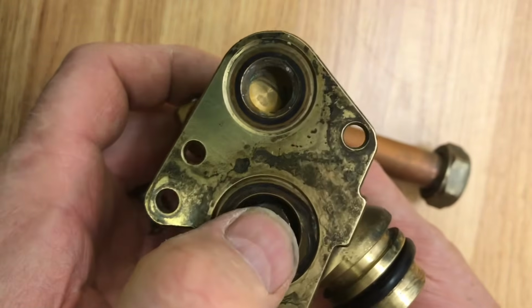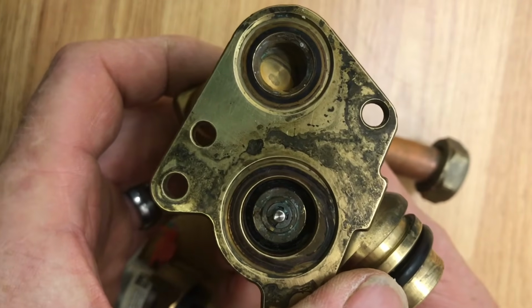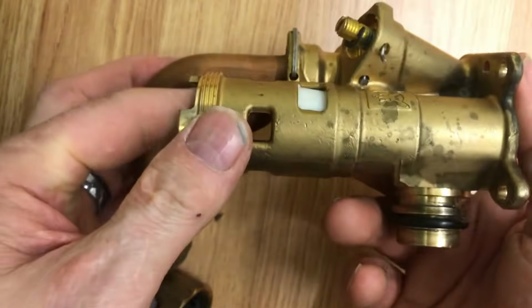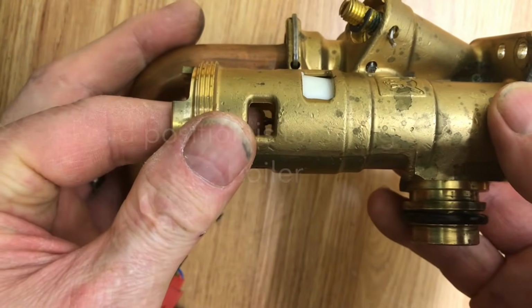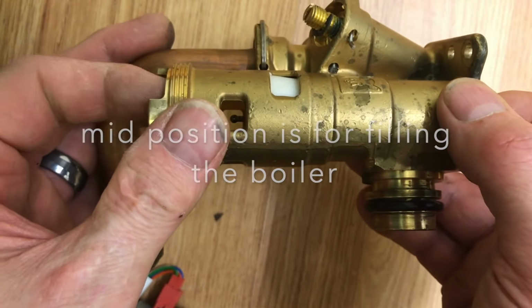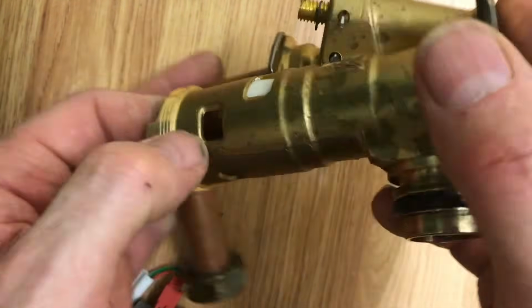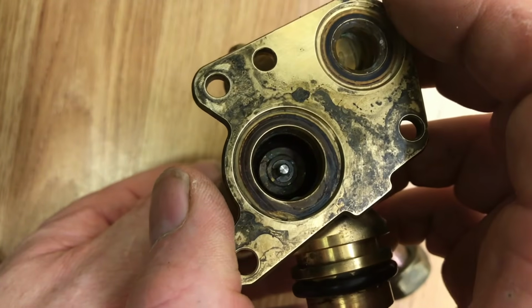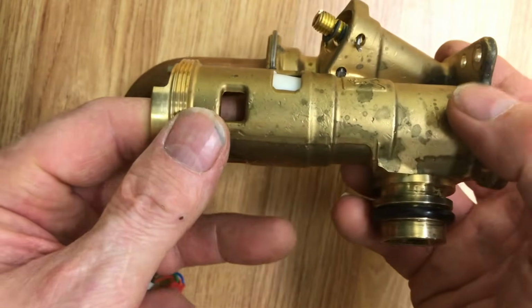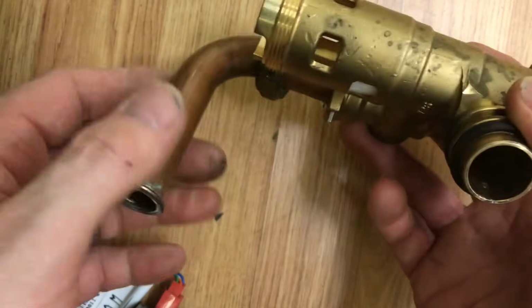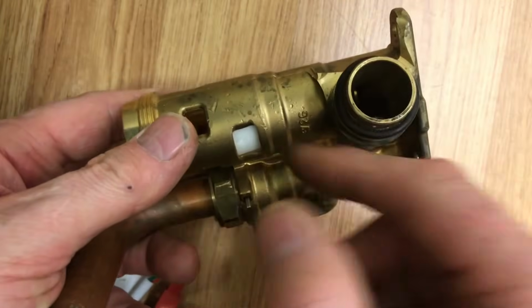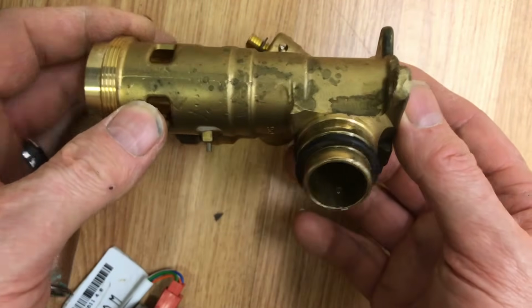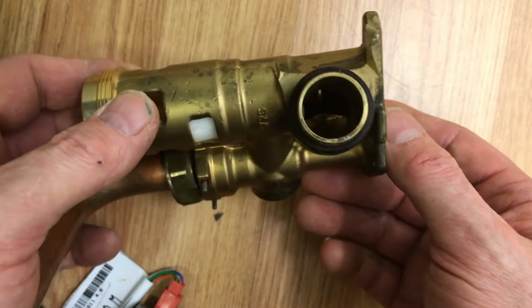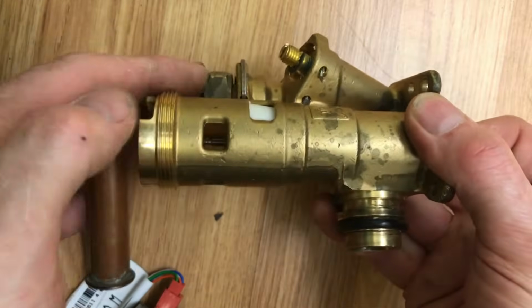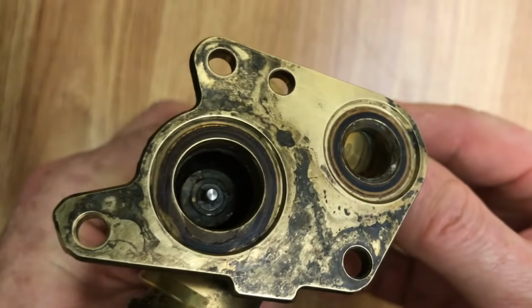So now we've got that off, we can have a look actually at the plate-to-plate heat exchanger. So this can go into 3 positions. It can go mid position, which is in the center, which allows you to have heating and hot water. If it goes all the way out, that allows it to go through the plate-to-plate heat exchanger. And if it's shut all the way across, it allows the water to come through here and go back into the heating circuit. So the heating circuit would flow through here, come through here, and then go through into the pump. Okay, so that's how the water would return. So coming up through here. Now the other hole here is the automatic bypass.